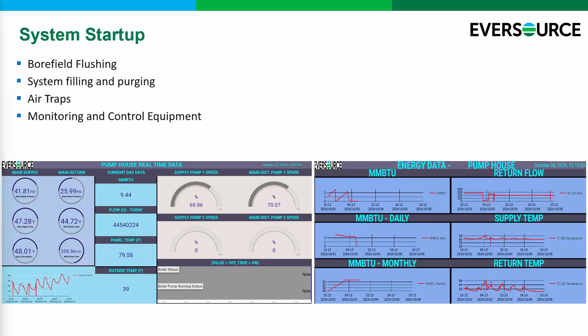On the building commissioning side, once the loop is on and running, now you've got to turn the buildings on as well. That followed a similar process: getting the equipment in, making sure the electrical and plumbing work was done. You then have to pressure test everything on the building side, because the last thing you want is a leak in one of these pipes carrying water and glycol that floods a basement or a room. It's not a great look to tell a customer, sorry, I flooded your basement, let me pump it out and try again. So there's a lot of testing, getting equipment on and running, then opening valves and tying into the main loop to make sure it's getting energy from the system.